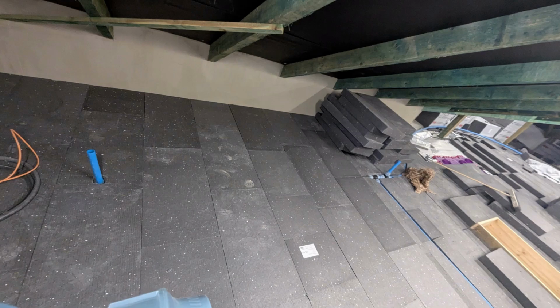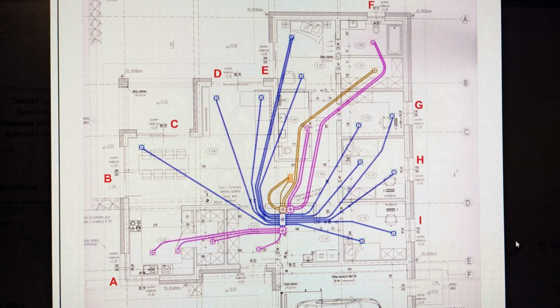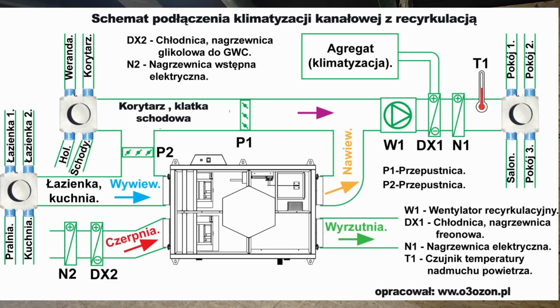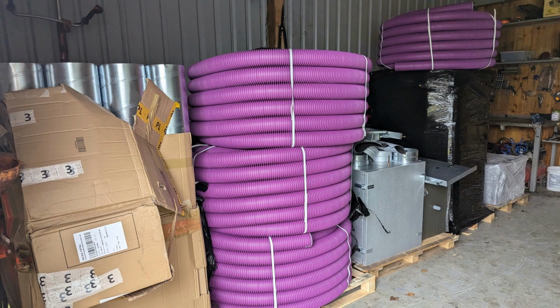The condensate drain, secured with a dry trap, has been connected to both the heat recovery unit and the glycol and freon chillers. I believe the system is relatively complex. It required quite a lot of work. However, after analyzing competitors' offers, and I did perform such an analysis, I believe that with the competition, I would have received at most a recuperator with pipes. But with Mr. Porozhevsky, I have a complete system with air conditioning and a GWC. Additionally, I also assumed that the cost of installation by some qualified team would probably double the cost of the entire project.